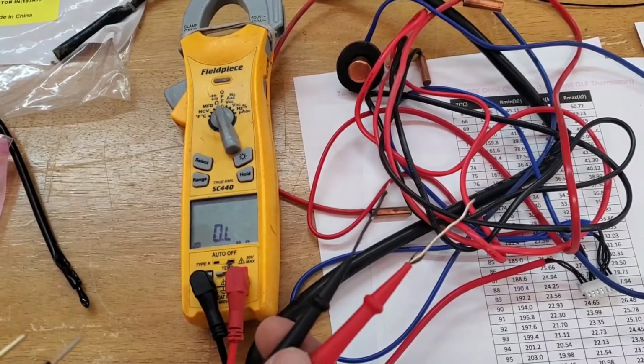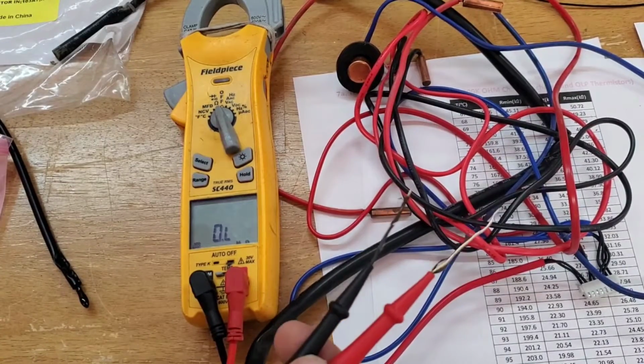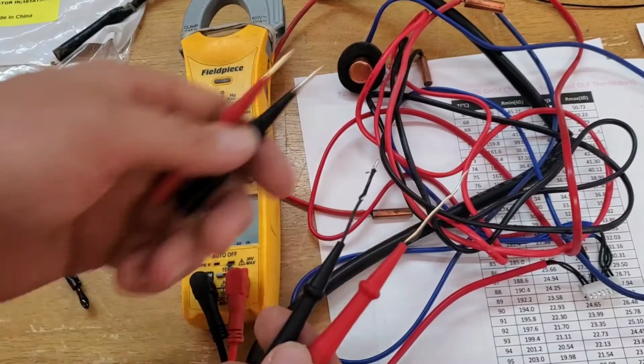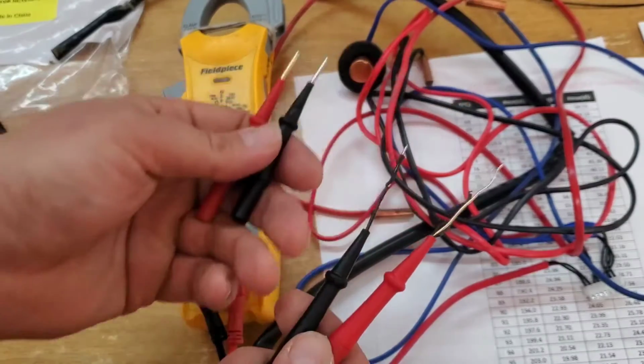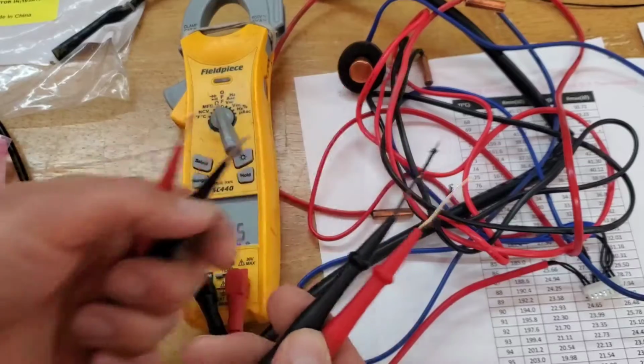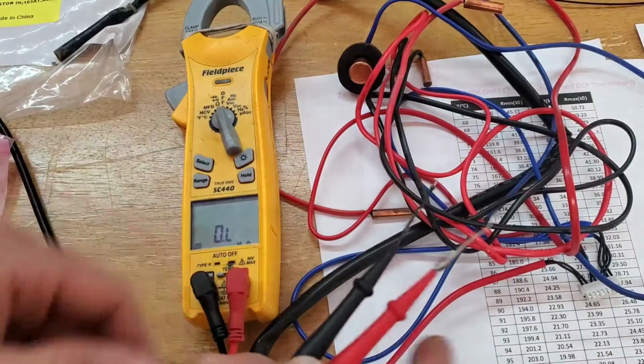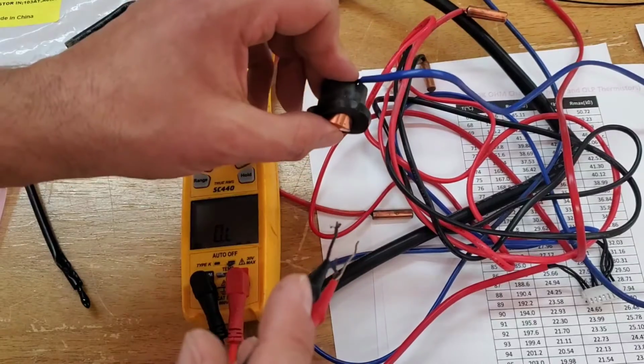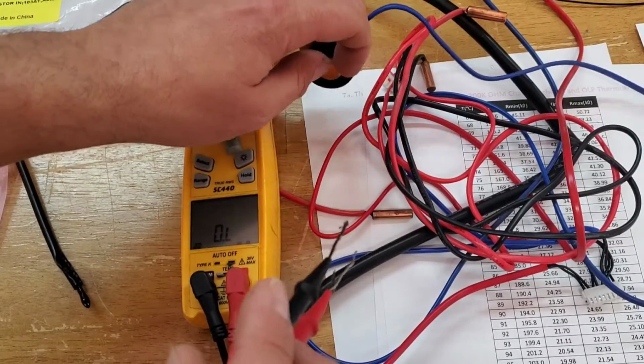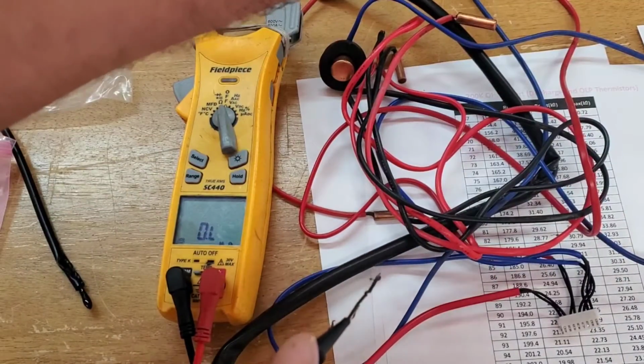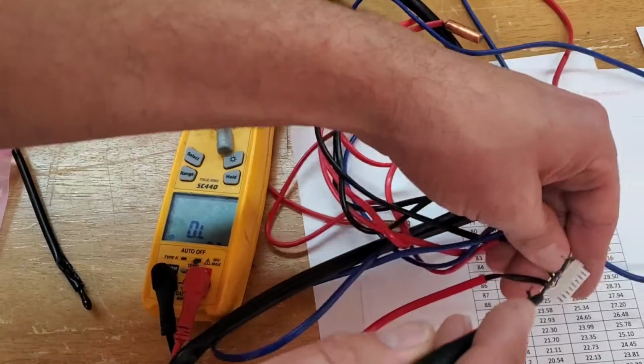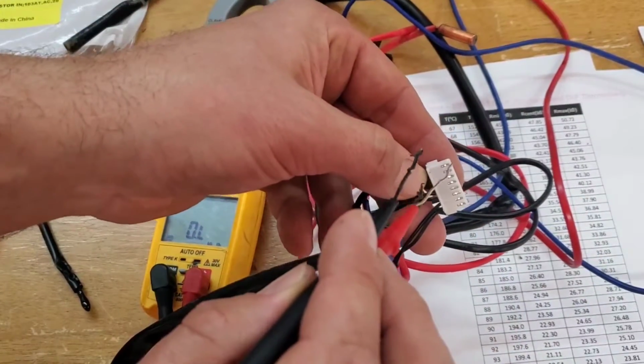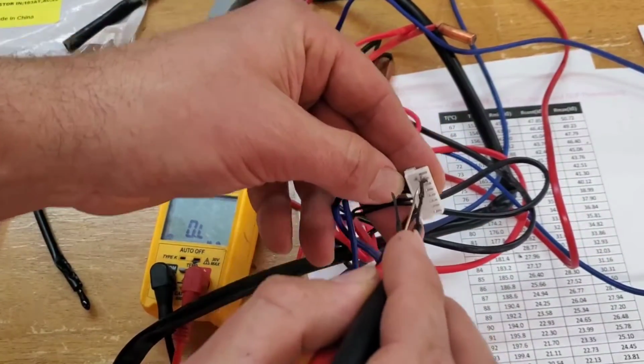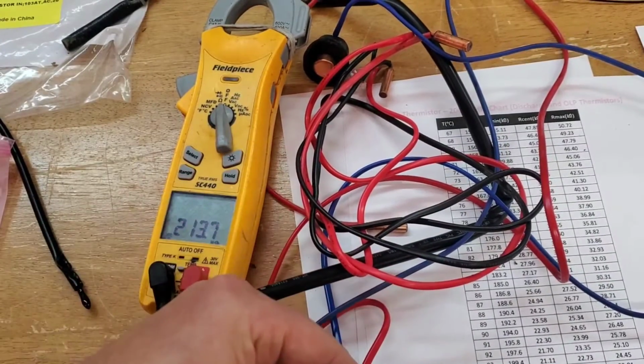All right, so what you're going to do is locate the thermistor that you're going to be testing. You locate the Molex plug where the thermistors are connected. Definitely make sure that you get your small, thin leads, that way you can actually fit them in there to take the measurement. So we won't need those. We locate the OLP sensor. We take the temperature, that way we know what the temperature is. Right now it's 71 degrees in here. So we locate it, and then we put our leads in here. We get them to where they're very, very still, and we read that measurement of 213.